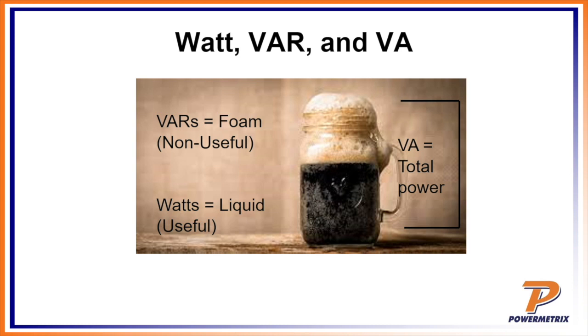So VA is the total power. Think of it as the foam plus the liquid is your VA. If you just look at the liquid, the actual root beer itself, that's the useful power, that's what's being billed to the customer. VARs is non-useful power, that's not being billed. So how do utilities compensate for that? They'll do power factor penalties, which is a good way to compensate when the customer is presenting a very inductive load.